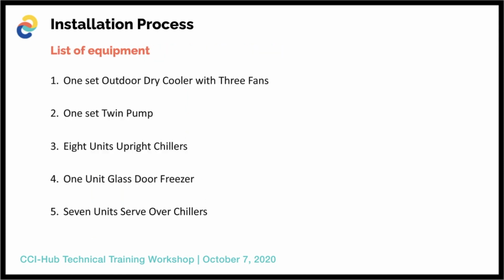Next is the list of equipment. First, one set of 3-fan outdoor dry cooler. One of the major parts of the Waterloop system is the dry cooler, which serves as heat rejection equipment; it blows away the heat circulating inside the stainless pipes. We used an 80 kilowatt capacity Güntner dry cooler for this project. Taking into consideration for calculating the capacity is the ambient temperature of 38 degrees Celsius and relative humidity of about 18%. Another major equipment is a set of twin pumps.